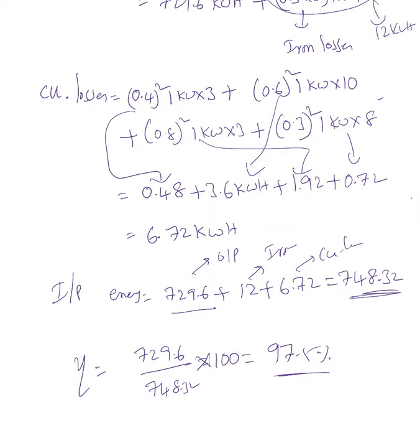If you look into a bigger load like our university, I'm assuming it is taking around 10 megawatt of power. If it is only 97.5% efficient, then 10 megawatts times the losses of 2.5%, which is 0.25, means you're losing around 0.25 megawatt of power.